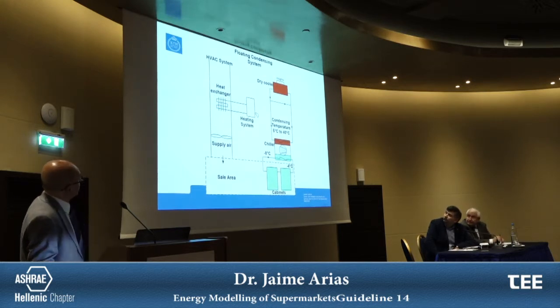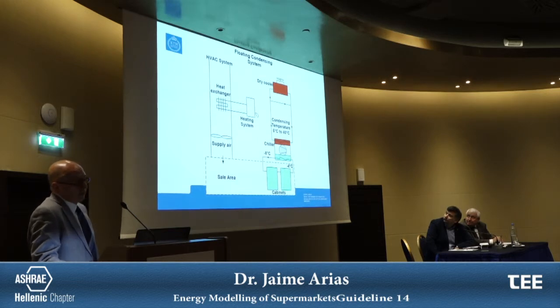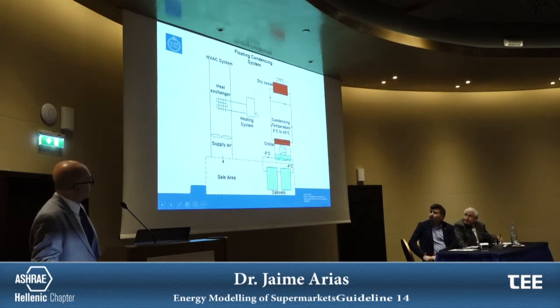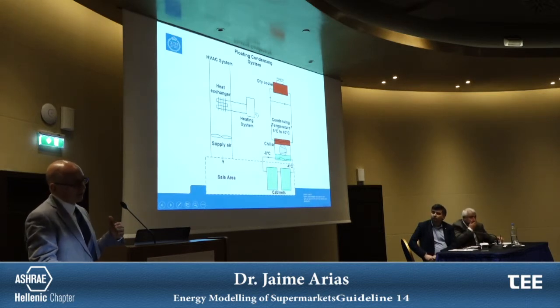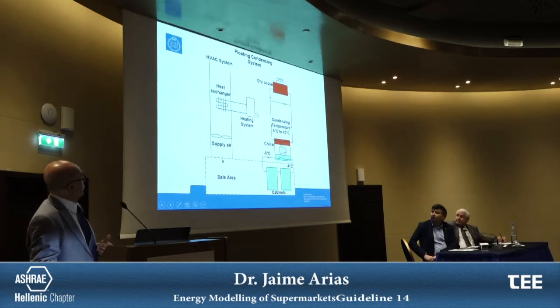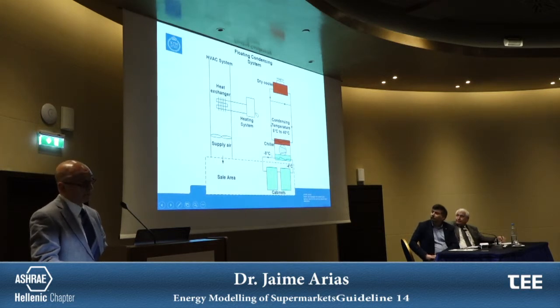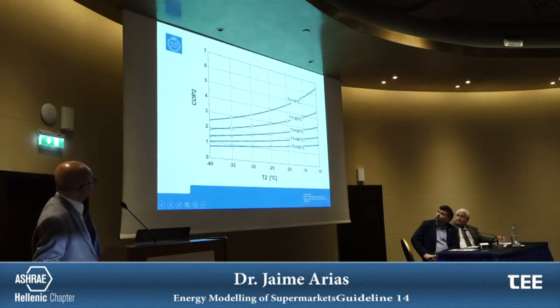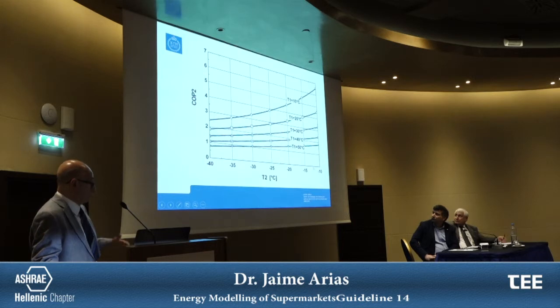And we started looking at this floating condensing system. And from the conditions we have in Sweden, we try to have a condensing temperature moving from 5 or 10 Celsius degrees to 40 Celsius degrees. And of course, we need to pay for all the heating we have in the building. And in this one, we try to study what happens with the coefficient of performance of the refrigeration system. So in this diagram, we have the coefficient of performance here. We have different evaporation temperatures, and we have different condensing temperatures. So for a normal, completely indirect system, we have an evaporation temperature of about -12, so we are here, and we have around 40 Celsius degrees as the condensing temperature.